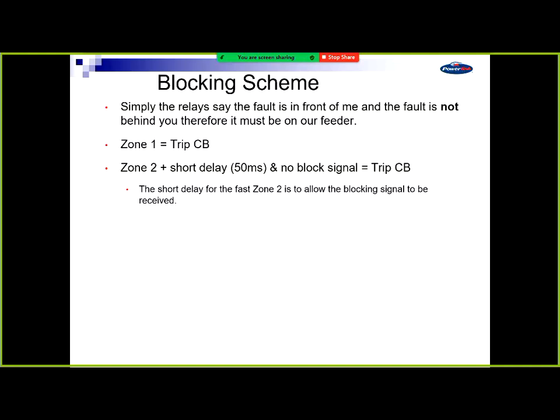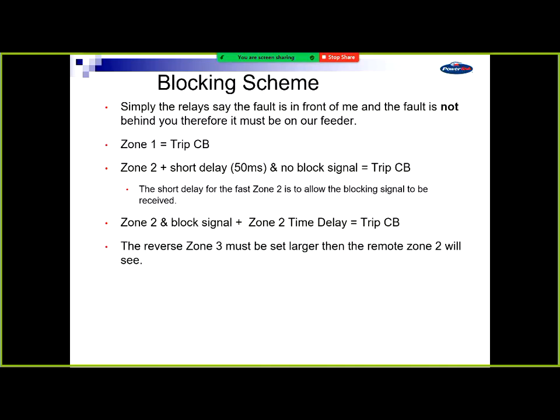If we don't get a signal from the other end, we go quickly. If we get a blocking signal, we do not. So I see it in zone 2. You see the fault behind you, so you do a setting for reverse zone 3. You set the signal behind you. Has that got it up there? Yep. You tell me the fault's behind you, I don't go quickly. You tell me nothing, and I go. So the fault's in between us on a phase conductor that we're sending PLC.